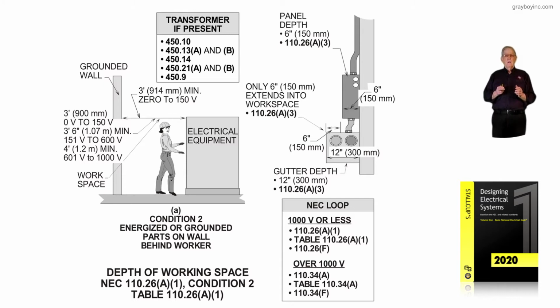see in the diagram. But to make sure that we're providing the appropriate clearances and working space and location and installation of transformers, we would review the boxed-in information titled "Transformer if present." We would look at 450.10, we'd have to have the appropriate grounding and guarding. 450.13 A and B divides that transformer into 112.5 kVA or less, or over 112.5 kVA. And then 450.14, we'll see as we get into this presentation, is where a disconnect is required for the transformer.